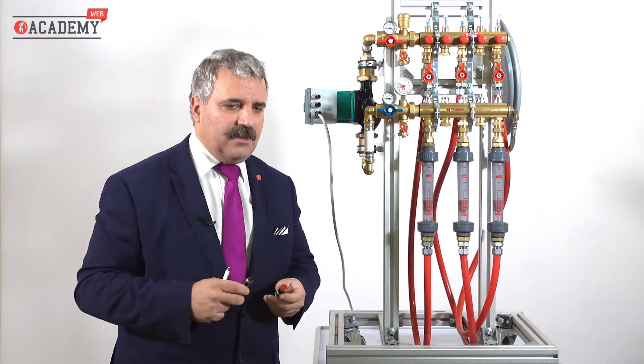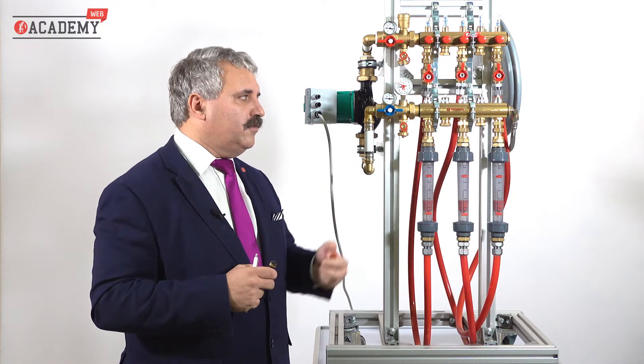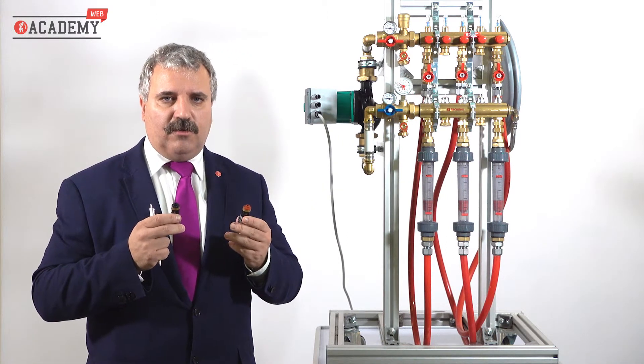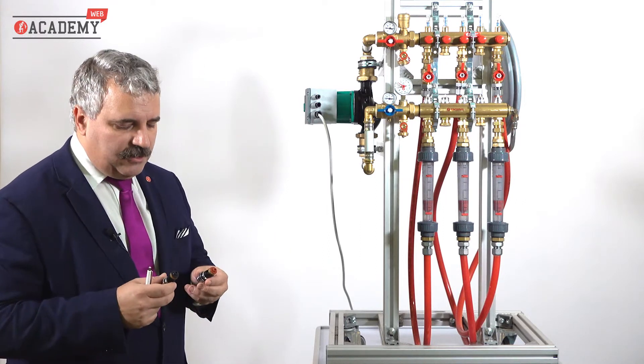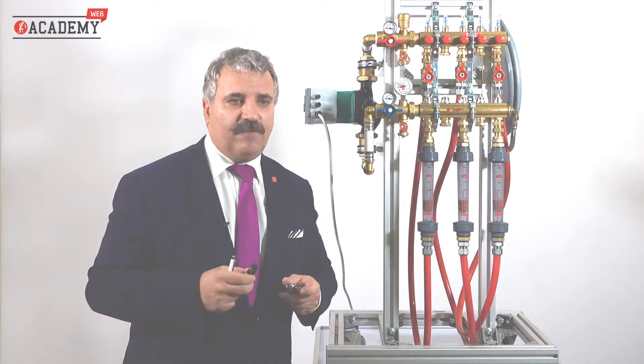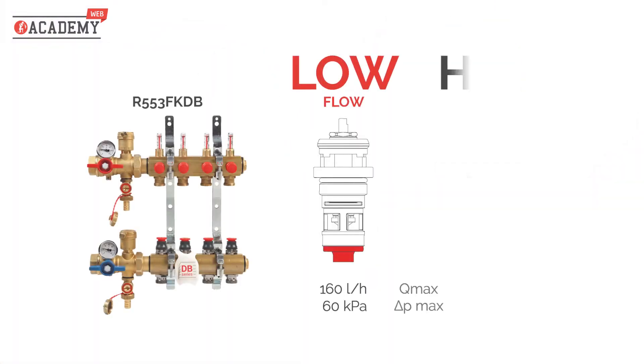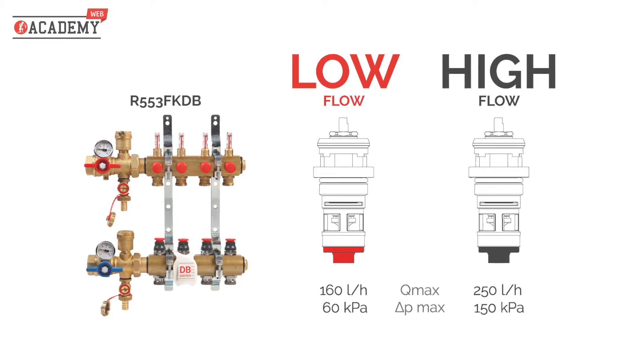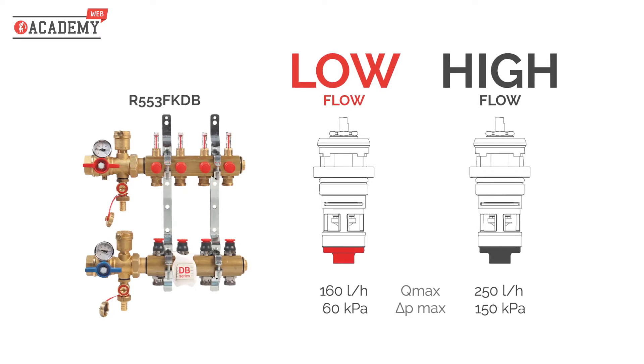To show you the main features, we have here a typical manifold for radiant floor applications with the dynamic balancing cartridges installed in the return manifold incorporating our DB technology. There are two flow rate ranges: the low flow version up to 160 liters per hour with a maximum differential pressure of 60 kilopascal, and the high flow version up to 250 liters per hour with a maximum differential pressure of 150 kilopascal.